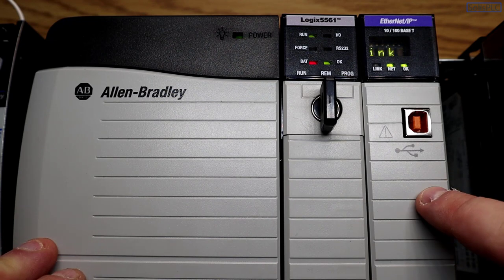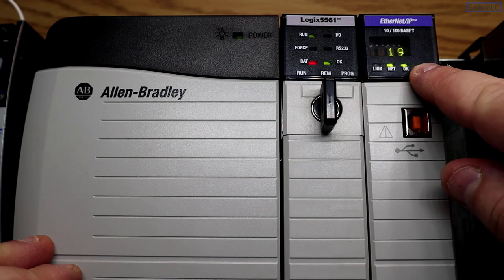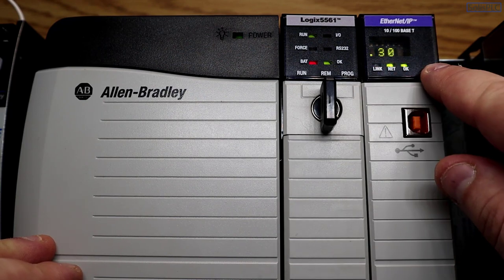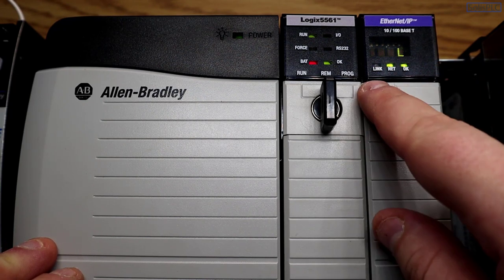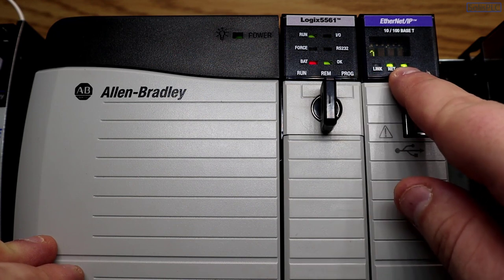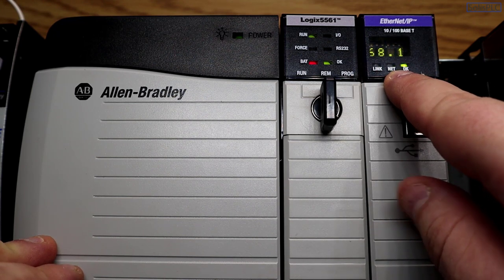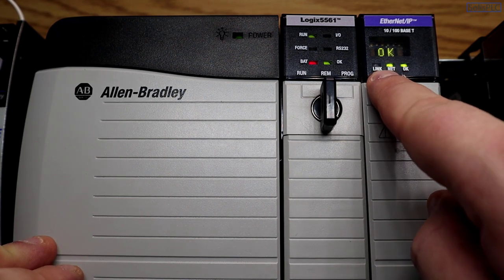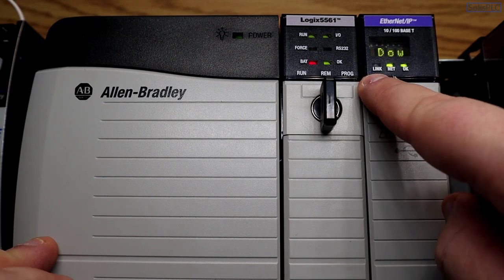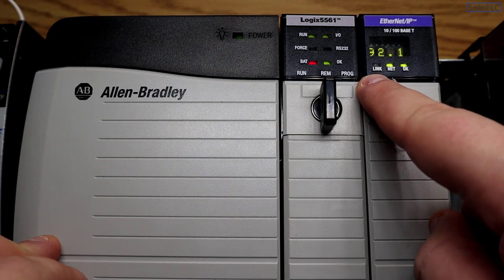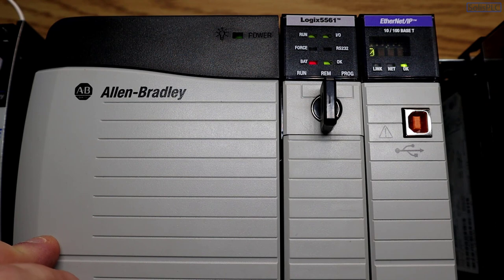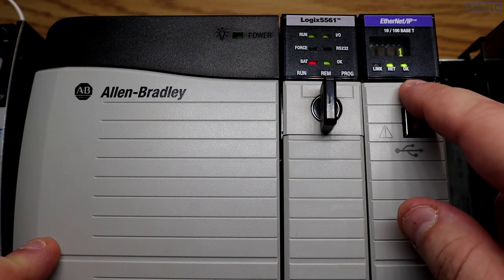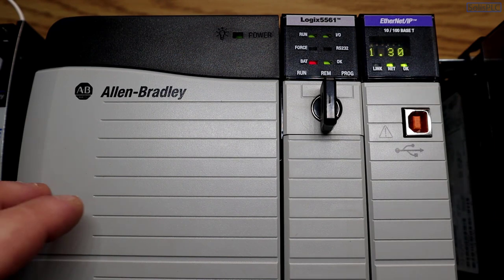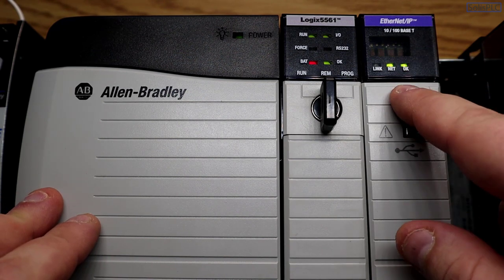So the first thing we're going to notice is that on the EN2T card as well as the EN3TR card, you're going to get a display of the IP address directly on the card. You're not going to have this on the ENBT or the ENET cards, which makes it a little bit difficult to figure out the IP address once you've purchased this card from a third party and they have already set this IP address through BootP or other means.